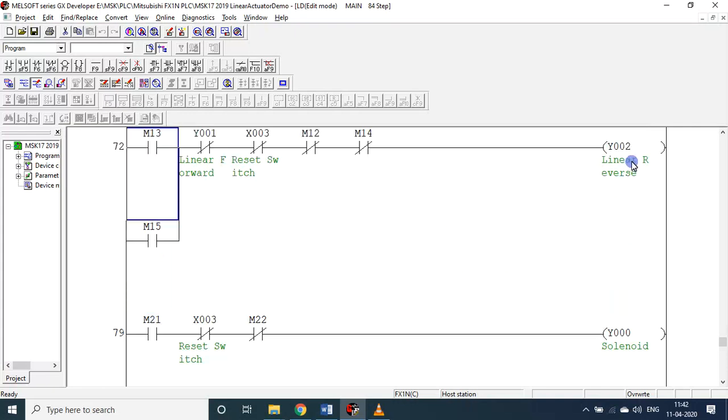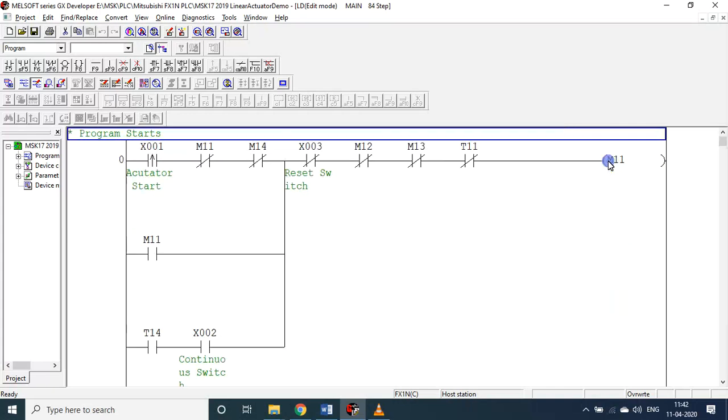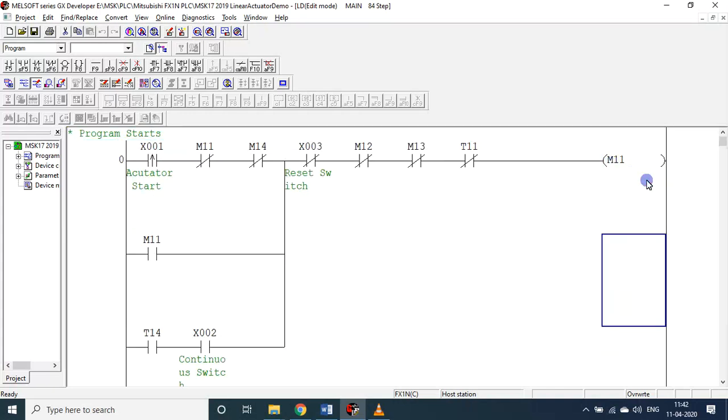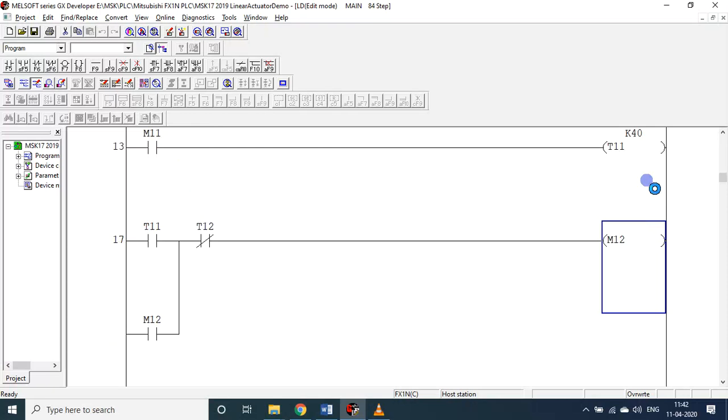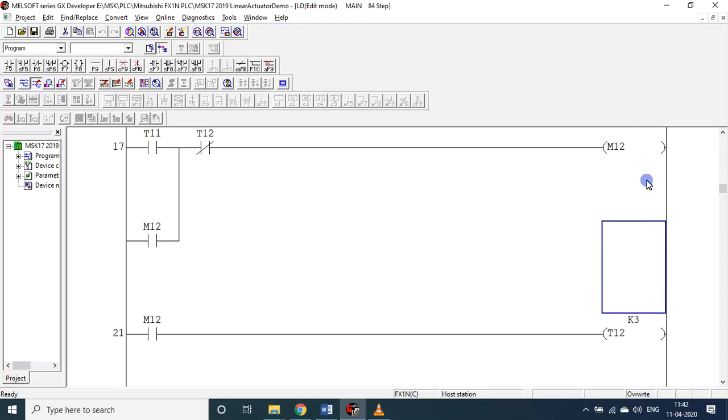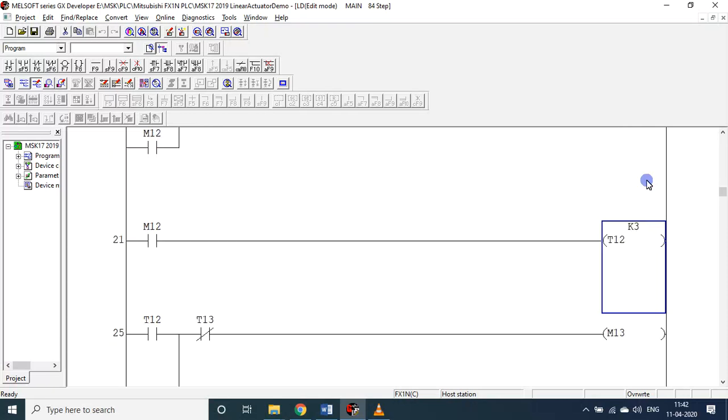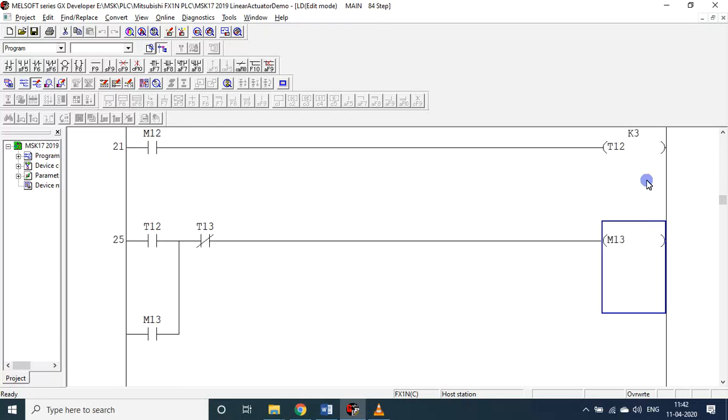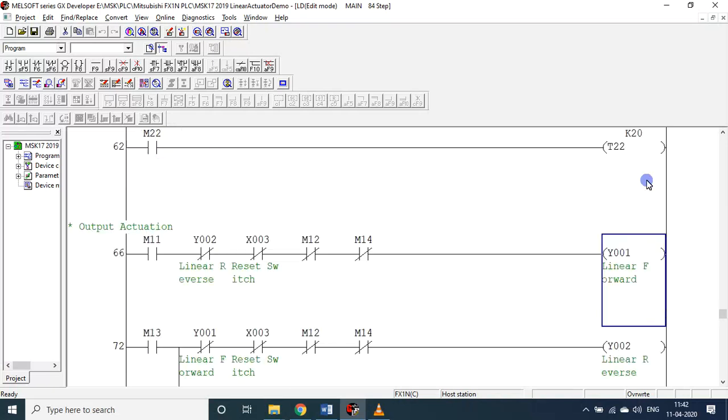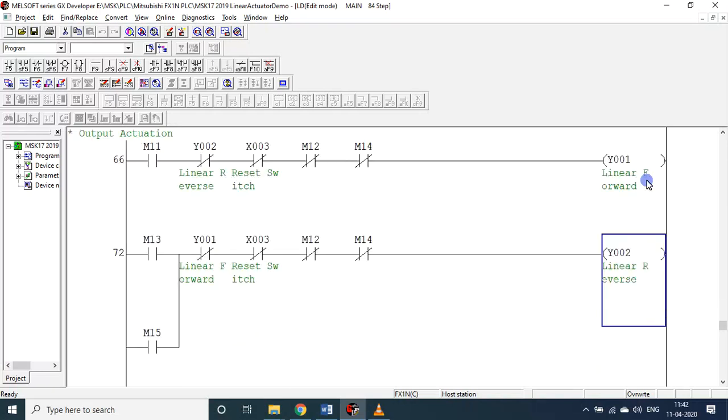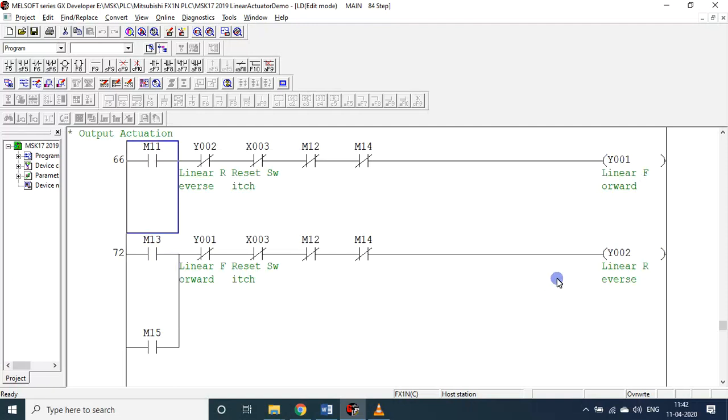In M13 the linear motor will be in the reverse direction. I have to change the polarity. M11 works for four seconds - K40, 40 means four seconds - then a brief delay of 0.3 seconds. After that M13 starts. M13 is linked with Y2, the reverse motion for the same linear actuator.